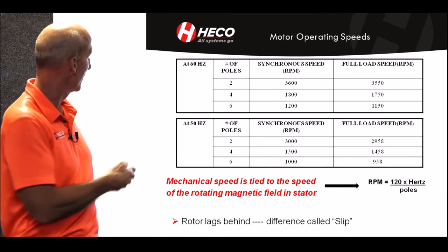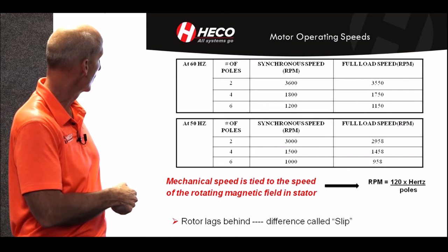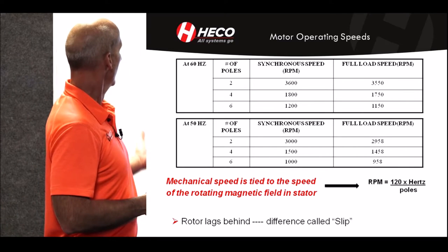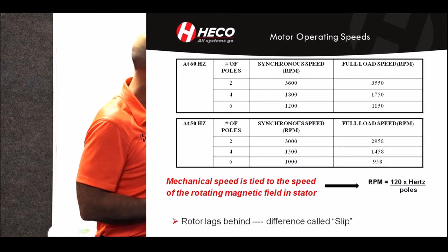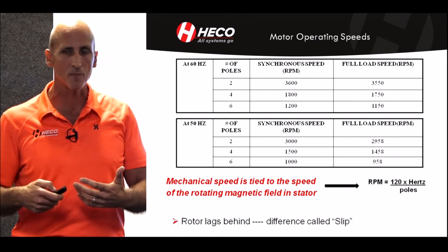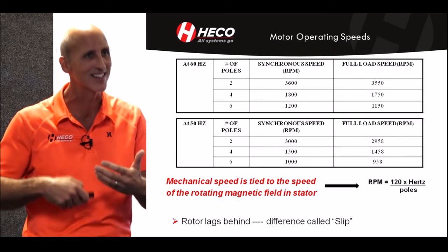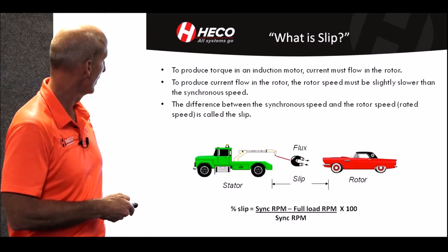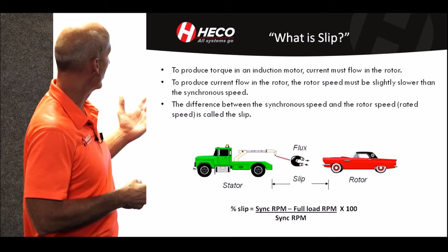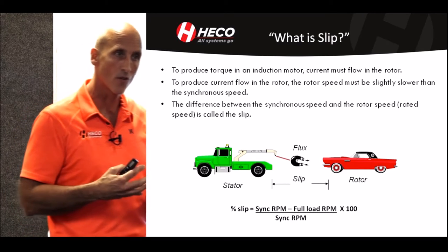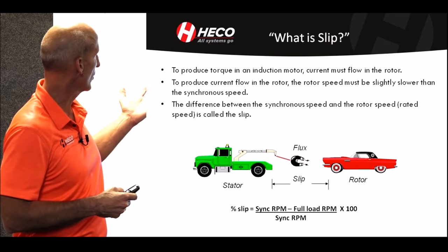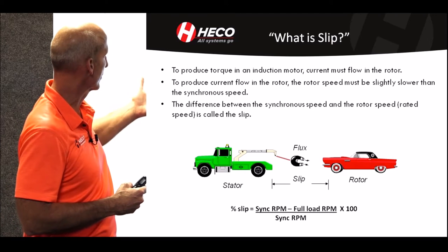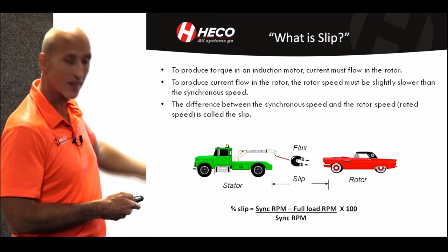Basic operating speeds go beyond this, but based on the number of poles: two-pole is 3,600 RPM, four-pole is 1,800, six-pole is 1,200. Full load speed RPM is going to be slightly less. The rotor is lagging behind the stator, so there's a slip involved. To produce torque in an induction motor, current must flow in the rotor. To produce that current flow, the rotor must be slightly slower than synchronous speed. The difference between synchronous speed and rotor speed is called slip, and it's calculated by that formula.